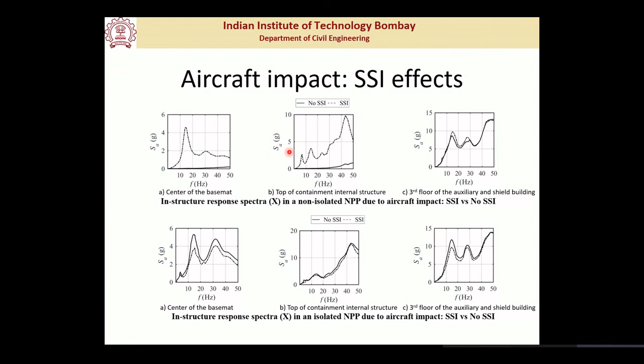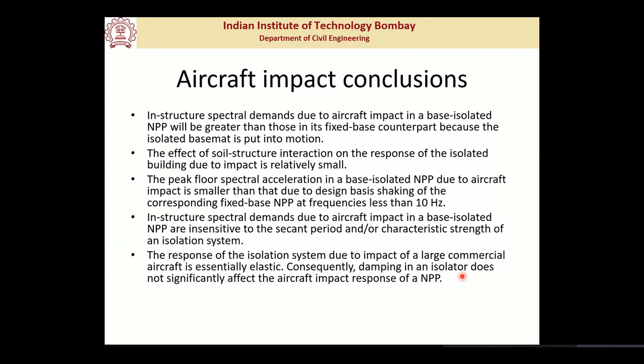So with this, these are the conclusions of the aircraft impact study. The structural spectral demands due to aircraft impact would be greater in a base isolated structure than in a fixed base structure. The effect of soil structure interaction is relatively small. The peak floor acceleration in a base isolated NPP due to aircraft impact is smaller than due to the design basis shaking of the corresponding fixed base NPP at frequencies smaller than 10 Hz. And the structural spectral demands due to aircraft impact are insensitive to the secant period or the characteristics of the isolation system. And the response of the isolation system due to impact of the large commercial aircraft is essentially elastic. And damping in the isolator does not significantly affect the response of an NPP.